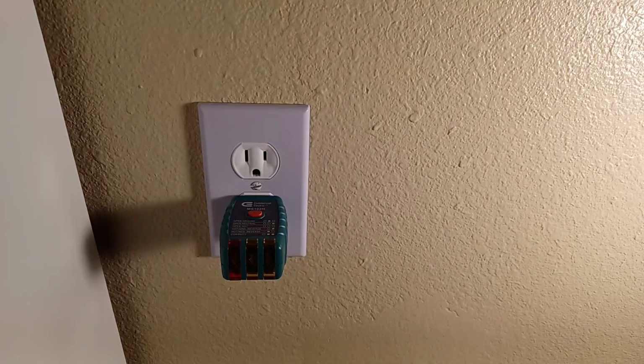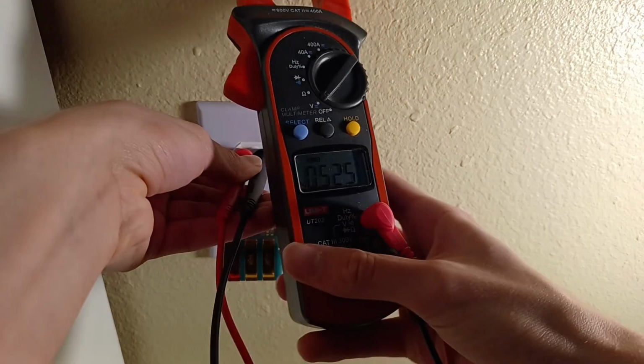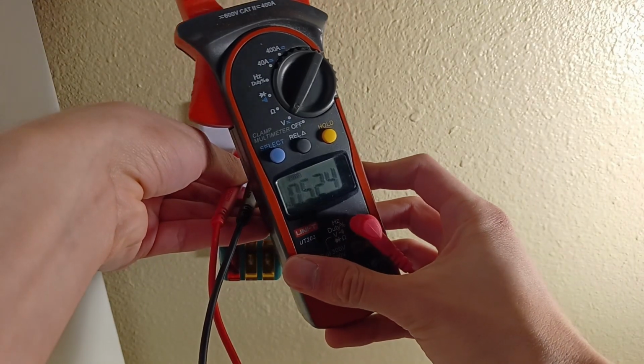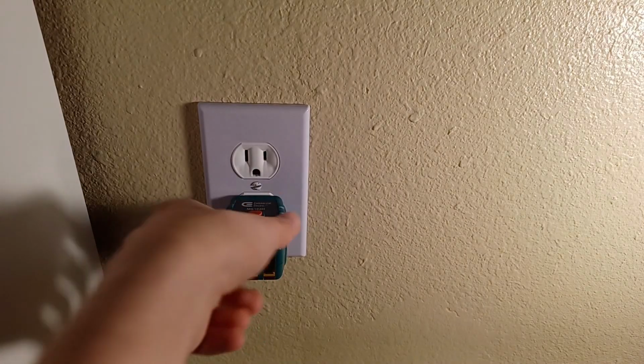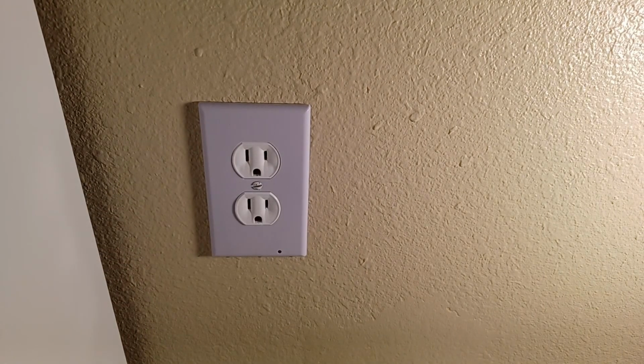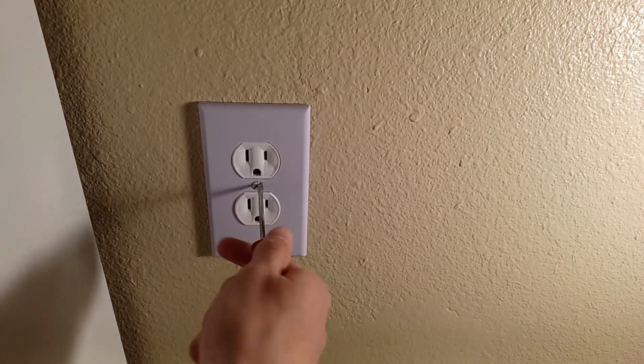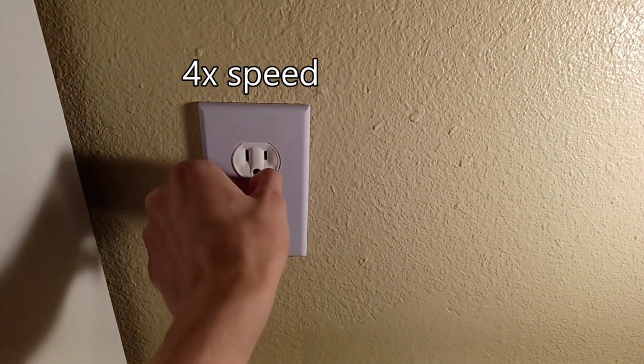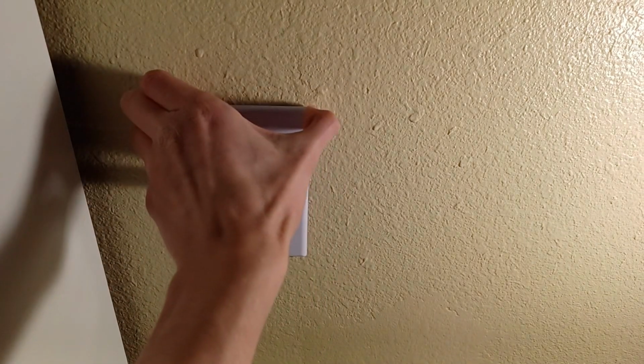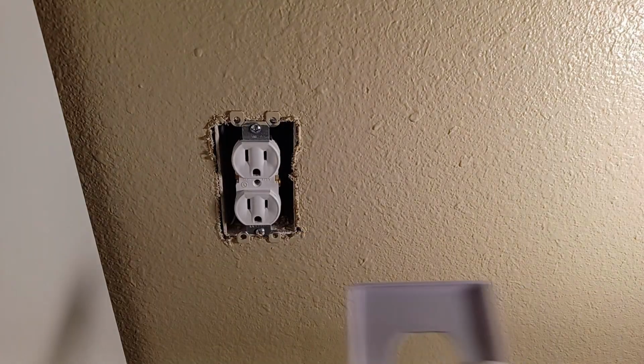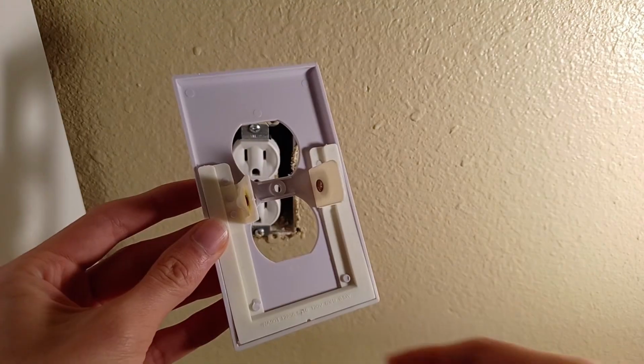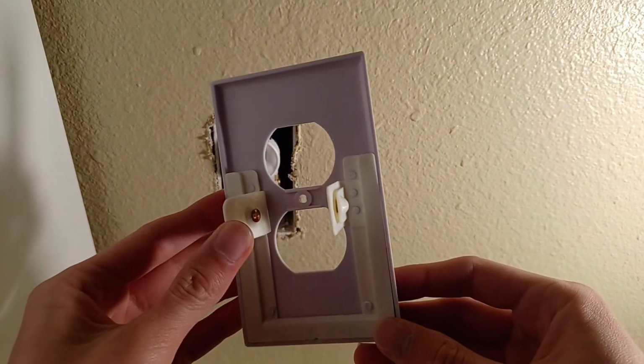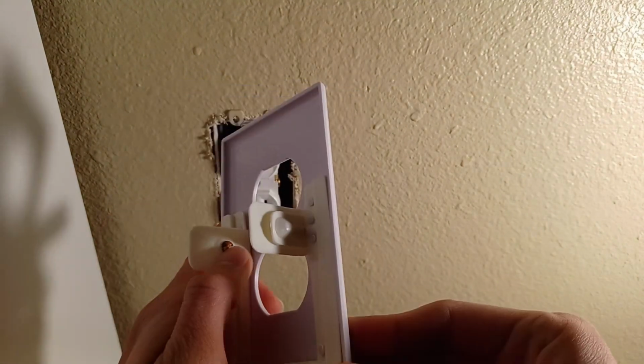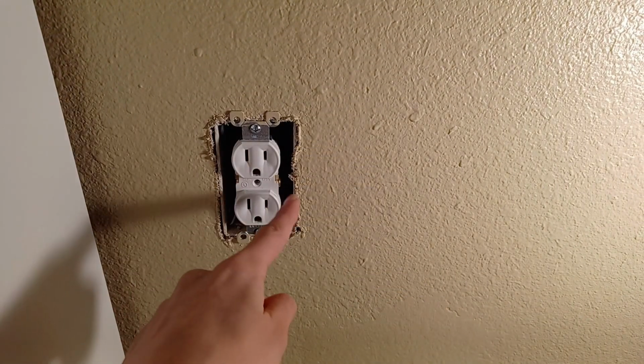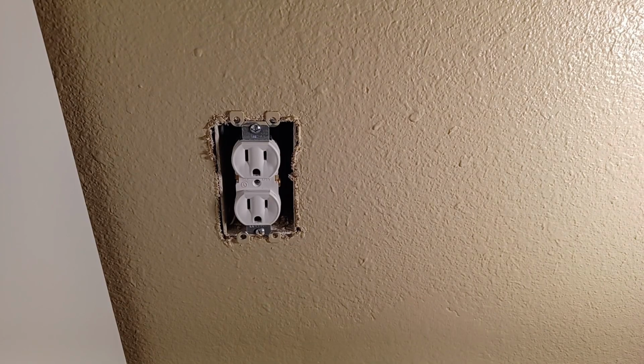Just to double check, I will use a multimeter, which is reading 0.5 volts AC, which is normal for capacitive coupling or leakage current, and is fine. I'll remove the screw and then pull this off. Now, this is the interesting part. The plate makes its electrical connection with the power outlet via these two copper pieces that press against the two sides of the outlet with the screws.